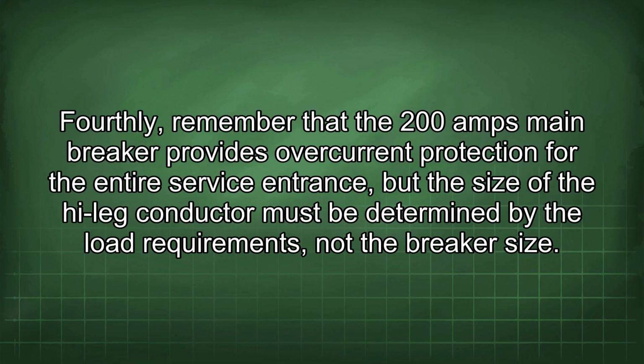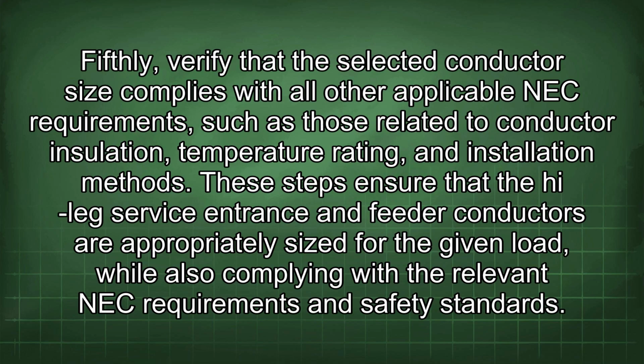Fourthly, remember that the 200 amps main breaker provides overcurrent protection for the entire service entrance, but the size of the high leg conductor must be determined by the load requirements, not the breaker size. Fifthly, verify that the selected conductor size complies with all other applicable NEC requirements, such as those related to conductor insulation, temperature rating, and installation methods. These steps ensure that the high leg service entrance and feeder conductors are appropriately sized for the given load, while also complying with the relevant NEC requirements and safety standards.